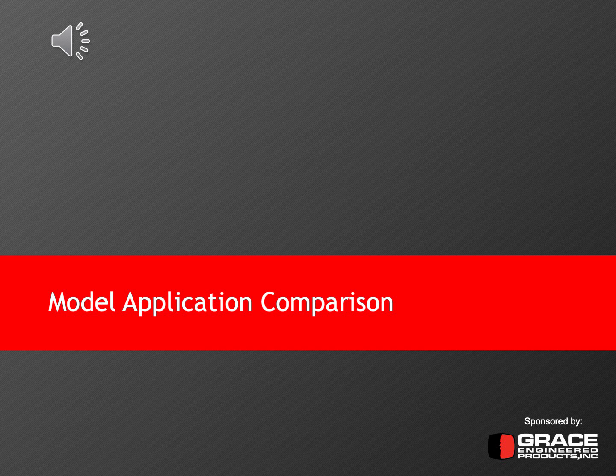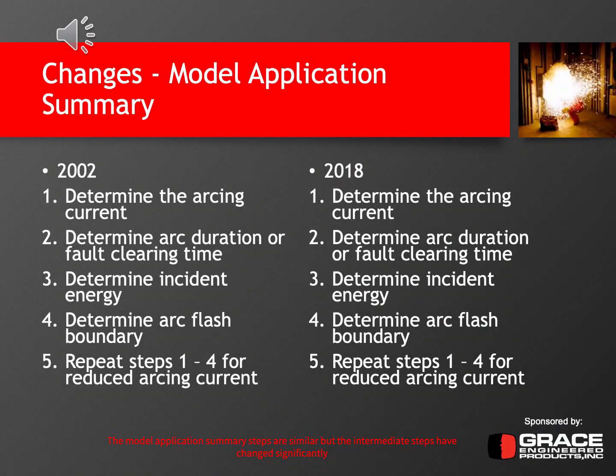The next thing we wanted to talk about was the application comparison, a model application comparison between 2002 and 2018. This is the summary of the model application presented in 2002 and in 2018. If you compare the two, they are exactly the same. Basically, the steps are the same; it's just that the working details within each step have changed. In both editions, you determine the arcing current, then determine the arc duration or fault clearing time based on the arcing current. That gives you the ability to calculate the incident energy, which then allows you to determine the arc flash boundary. Then you repeat the first 4 steps for the reduced arcing current. In 2002 that was the 85% rule; in 2018 it is the minimum arcing current calculation that you have to perform.